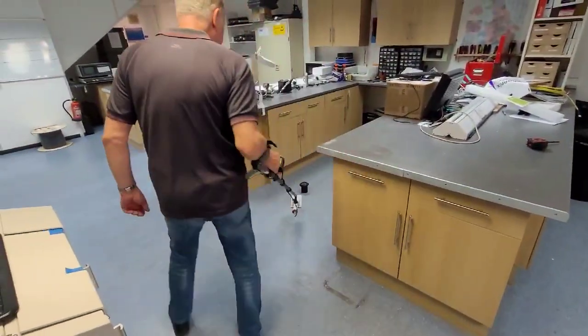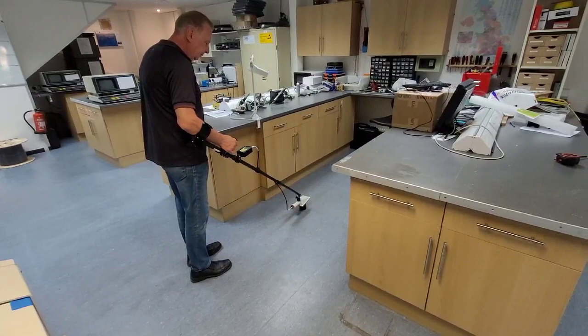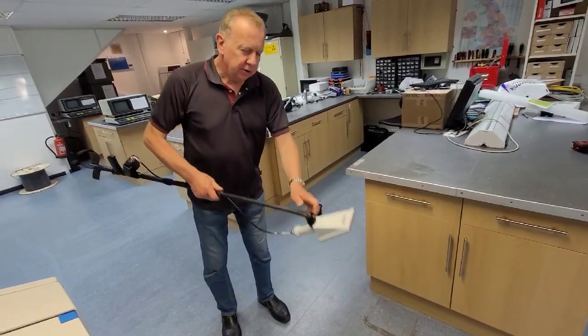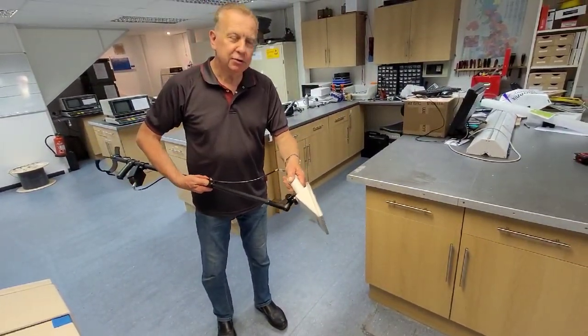And then, if you find the source — I've got a radio source here on the floor — it will simply activate and sound an alarm. It's fairly simple, and you can adjust the angulation of the probe here by the simple screw on the side. That ends my demonstration, thank you very much.